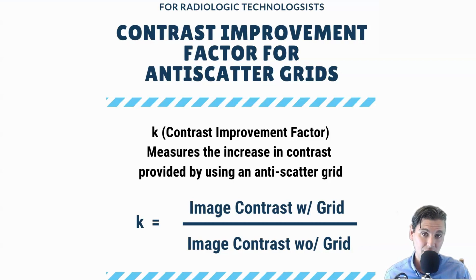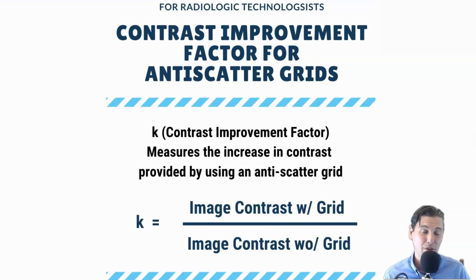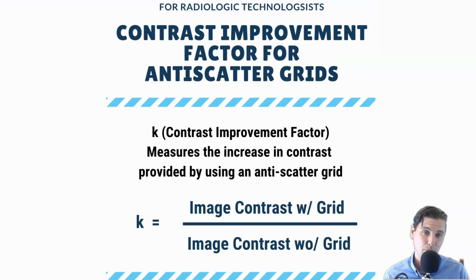Smaller, lower contrast lesions can be seen better if there's less background haze or fog in your x-ray images. We quantify this with the contrast improvement factor, which we call K. The contrast improvement factor is the image contrast with the grid compared with the image contrast without the grid. So if K equals 2, that means your contrast is going to be twice as high with the grid present than without it.